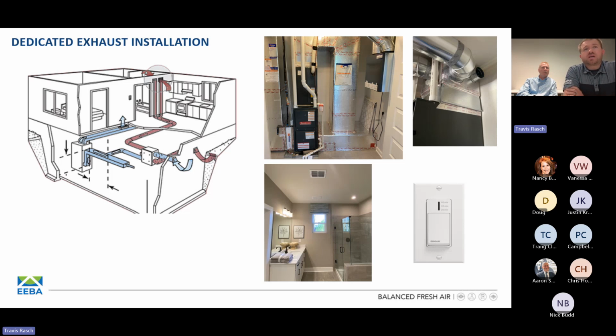The next is what we call dedicated exhaust. Just like the name states, we have dedicated ductwork running to various areas of the home. Pat hit on it earlier: typically our most polluted areas of the home are our bathrooms and kitchen areas, for the various reasons Pat mentioned earlier on the pollutant side of things. So it's typical that you will have your stale air extraction going back to the HRV or ERV, pulled from those areas. Then in this case, we still have our fresh filtered air coming from the HRV or ERV, and it can go either into the return side of the air handling system or into the supply side to, again, leverage the ductwork we've got for our forced air system.